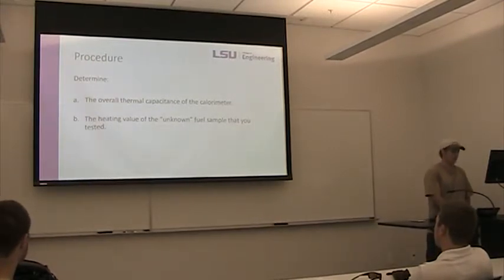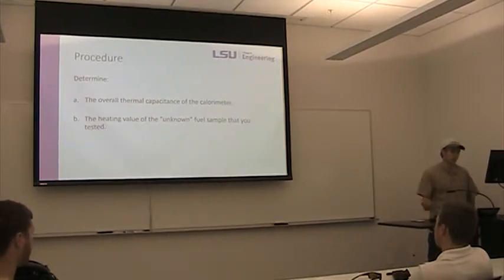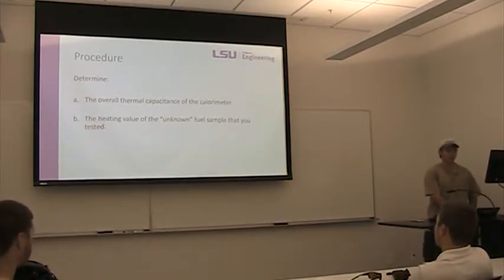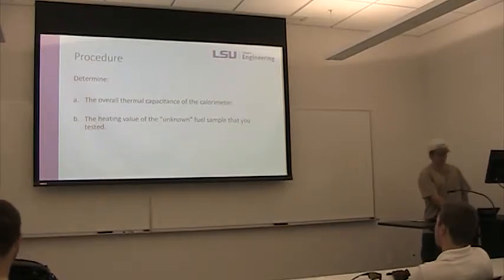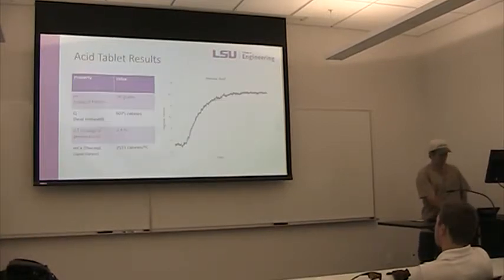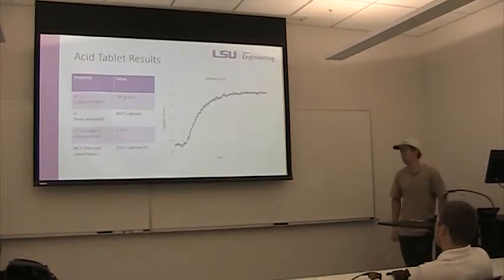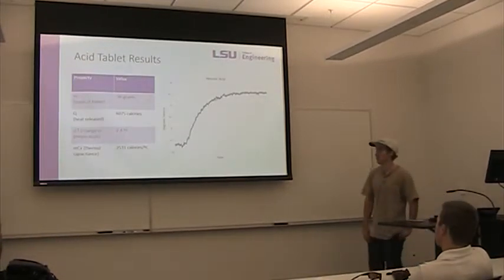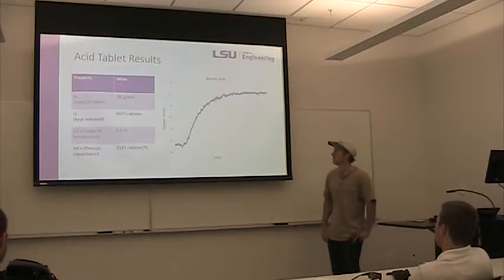Here is a recap of our procedure. Basically, we first determine the thermal capacitance of the calorimeter, and then, using that as a control, we can determine the heat release of the sample.